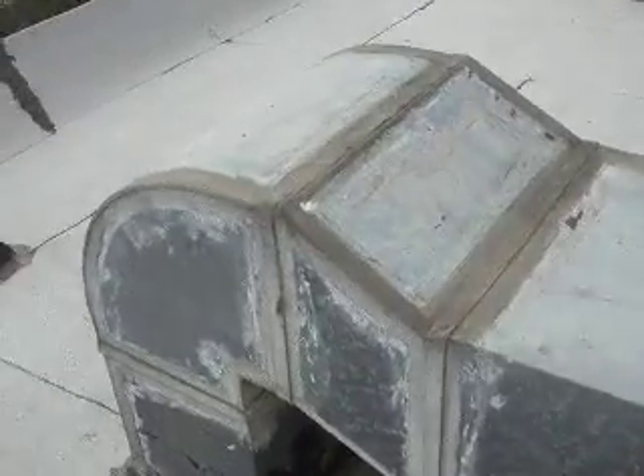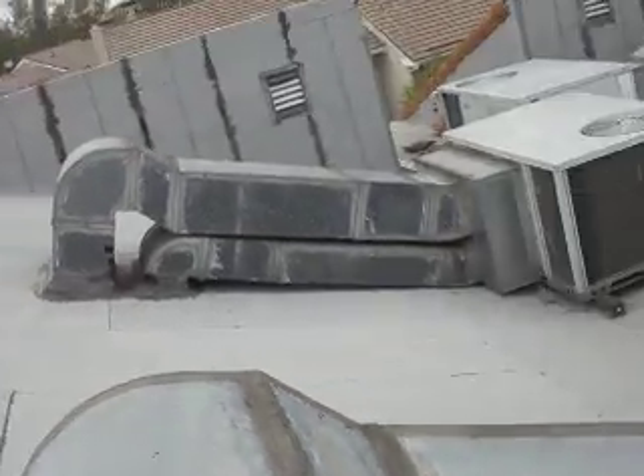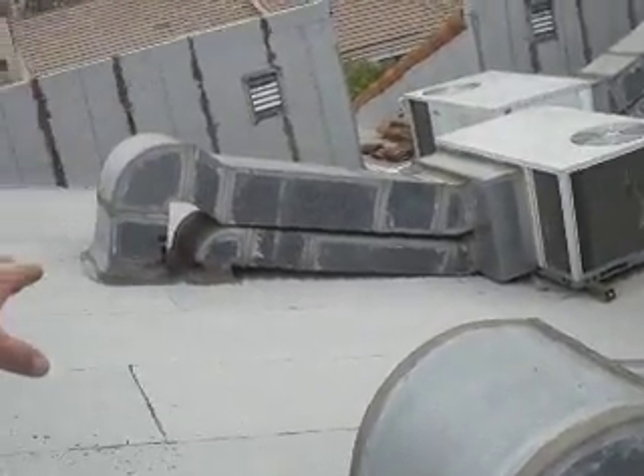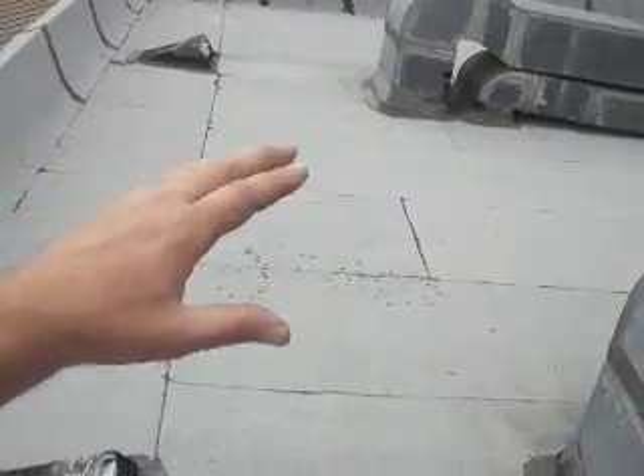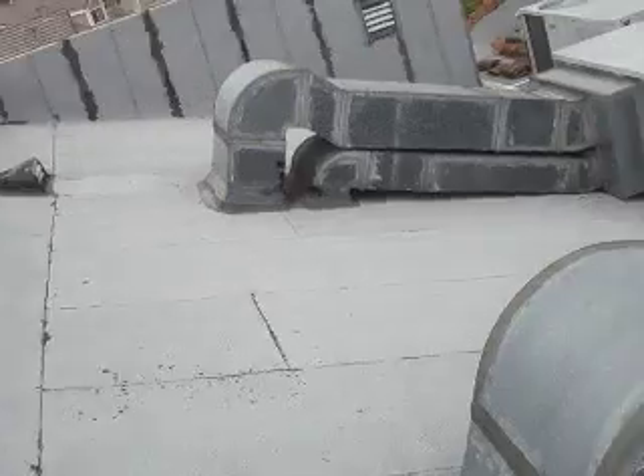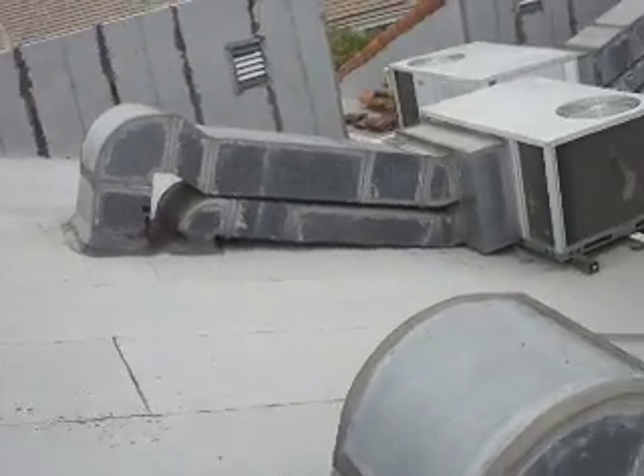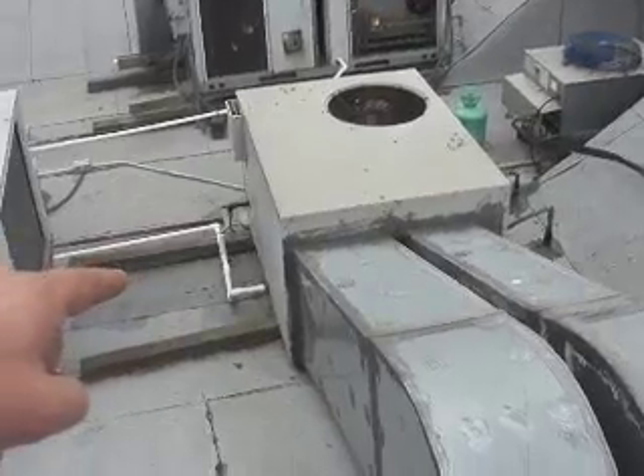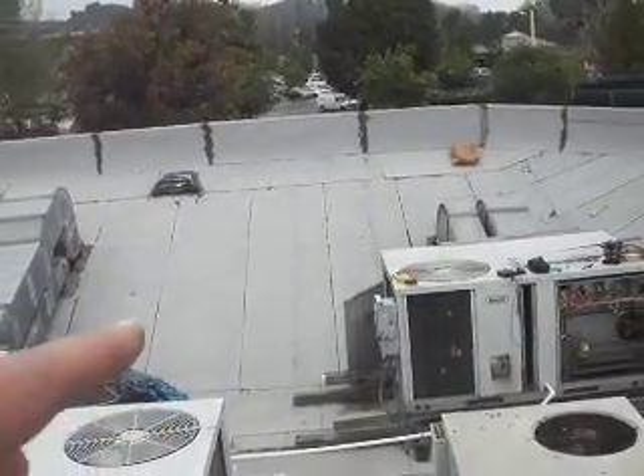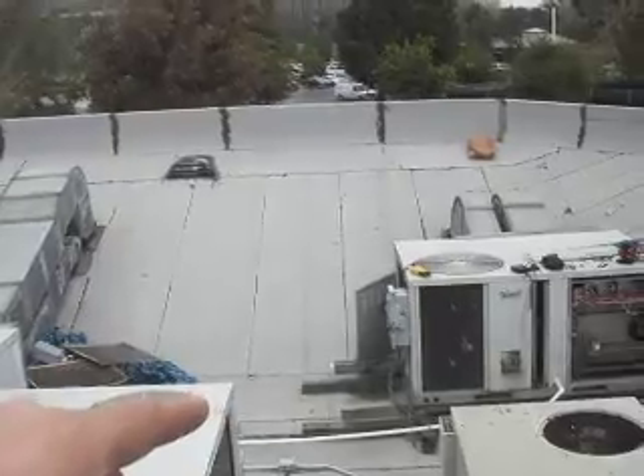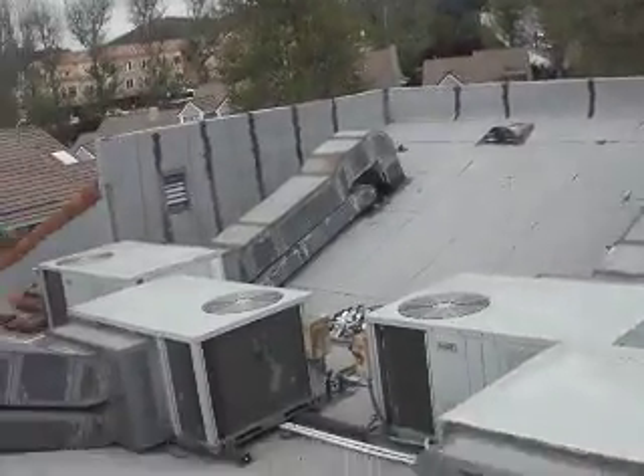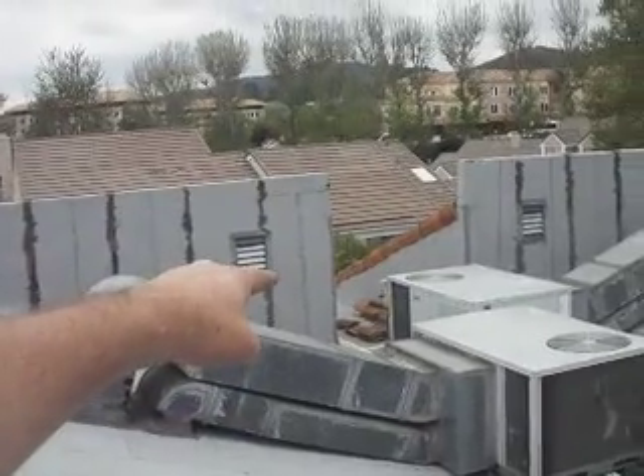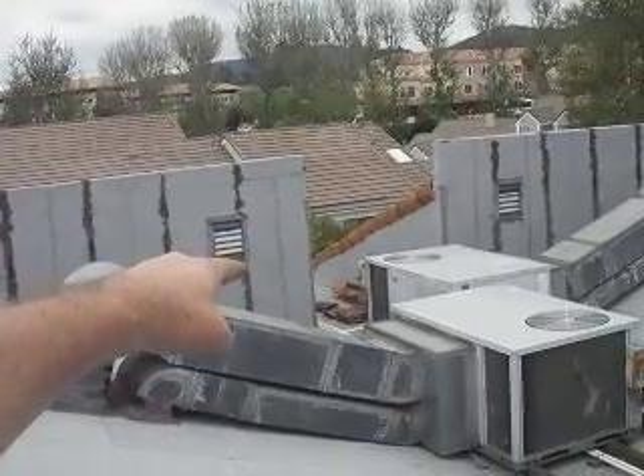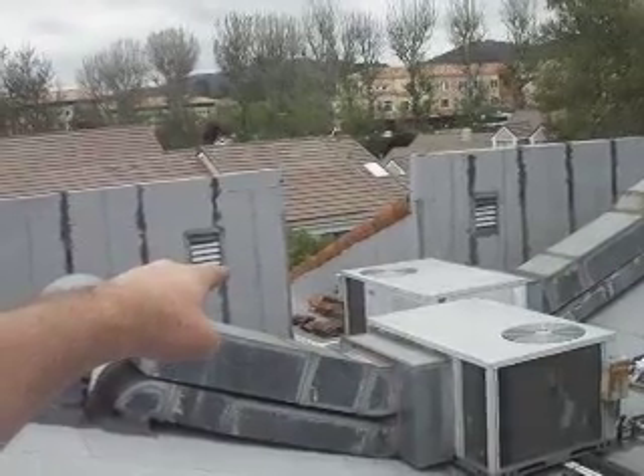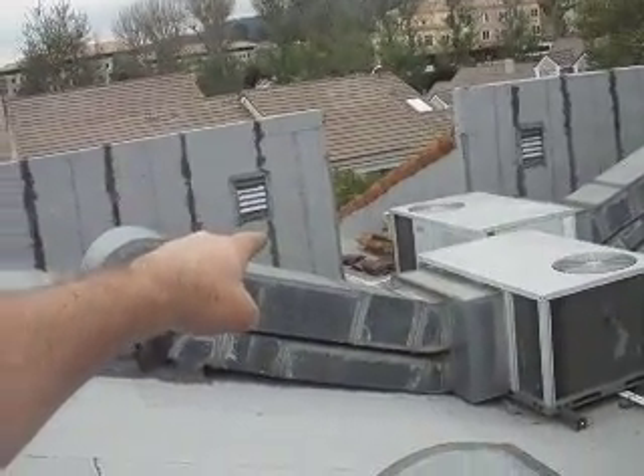Anyhow, the external ducting is not too bad. When we pulled all this equipment up off the roof while working on the roof, I re-insulated the insides of the boxes, so they're not too bad. But we need to really consider replacing at least this one for the lobby. I would really recommend replacing the one for the projection room, and at least this one out on the far side, the unit on the very end for Theater 1. That one's got a lot of leaks, and that compressor's questionable, but it works.